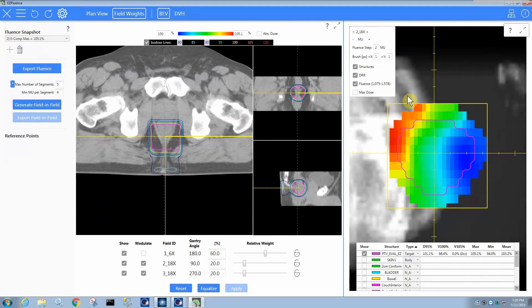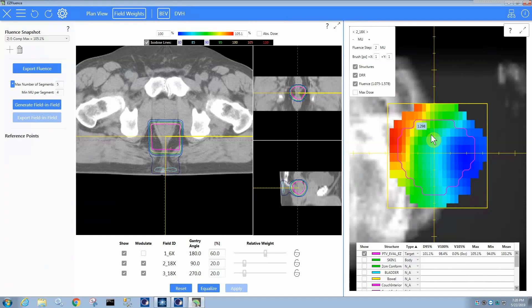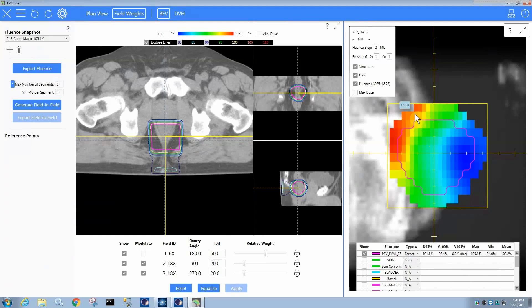If I go to the next field, what does this look like? It looks like a wedge, right? Because you have a higher dose here on this side and then this side. And so that's almost exactly what it's doing is the optimizer sees that it needs more coverage in the structure back here where the percent depth dose of the PA field is not getting enough dose. And so EasyFluence automatically creates a wedge-like fluence pattern. Now it's better than a wedge though, because a wedge would be the same intensity from top to bottom. But here you can see EasyFluence has a differing intensity where it needs to in order to get better coverage.